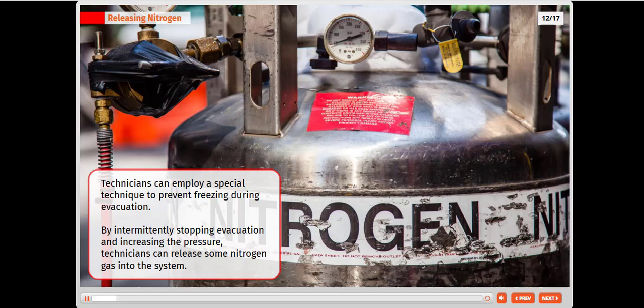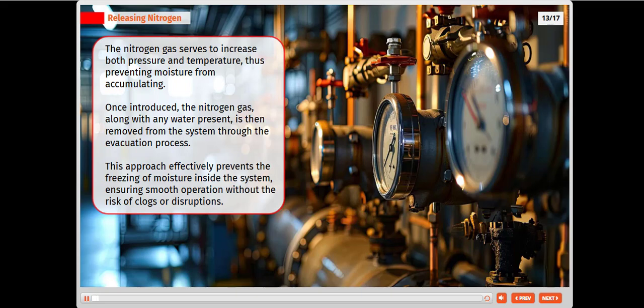Technicians can employ a special technique to prevent freezing during evacuation. By intermittently stopping evacuation and increasing the pressure, technicians can release some nitrogen gas into the system. The nitrogen gas serves to increase both pressure and temperature, thus preventing moisture from accumulating. Once introduced, the nitrogen gas, along with any water present, is then removed from the system through the evacuation process. This approach effectively prevents the freezing of moisture inside the system, ensuring smooth operation without the risk of clogs or disruptions.